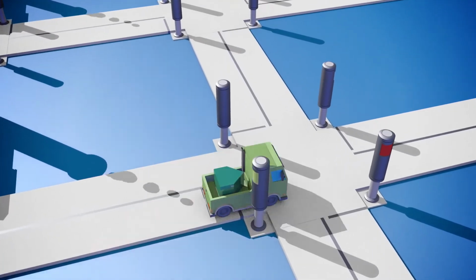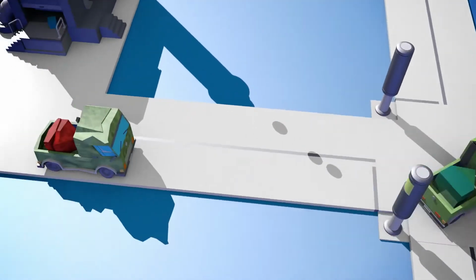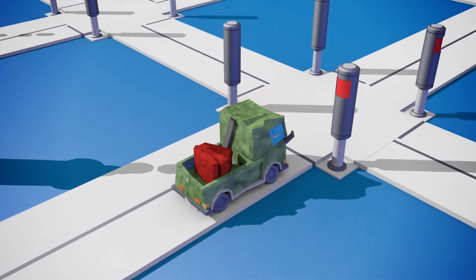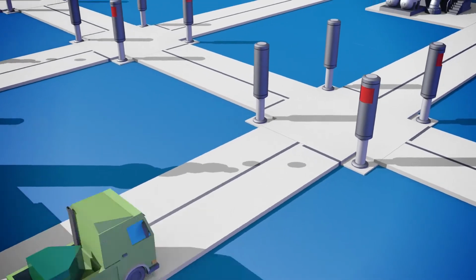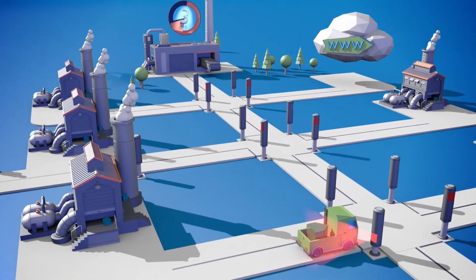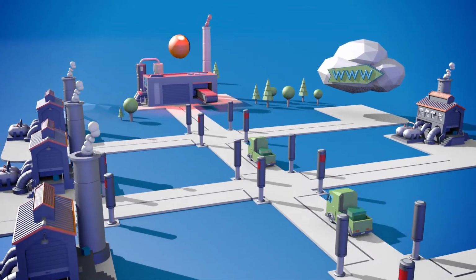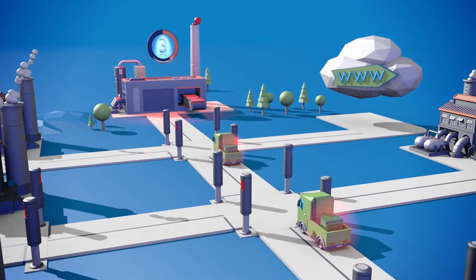Switches operate almost exclusively in store and forward mode. This means that telegrams are completely checked for CRC errors or fragments prior to the routing. If there is an error, they are deleted. As a result, a time delay can be expected at each switch transition. If the planned arrival of the telegram is delayed, this is referred to as jitter.